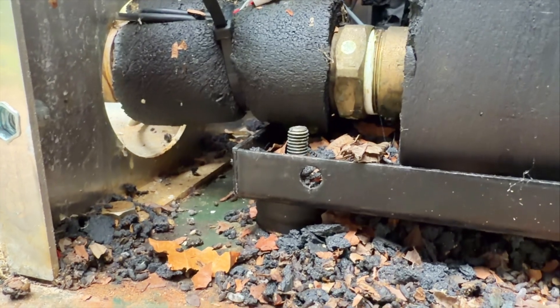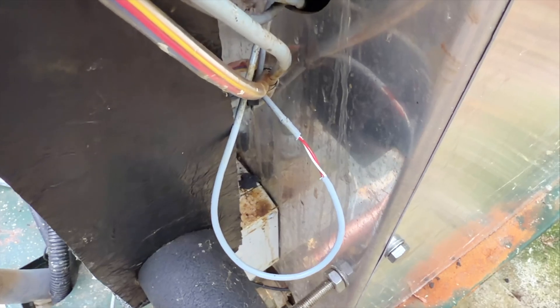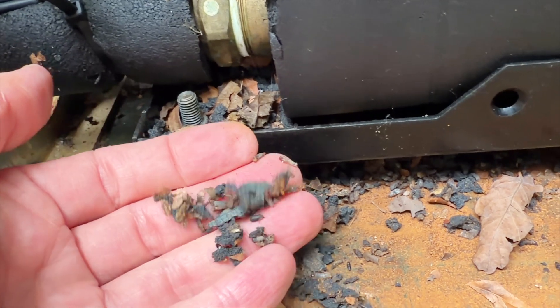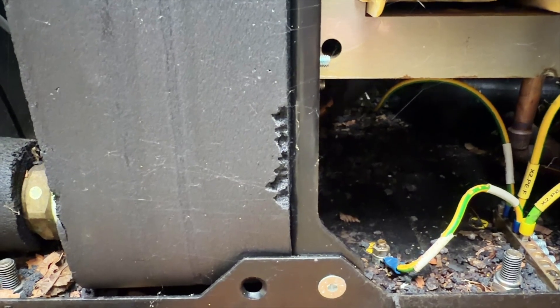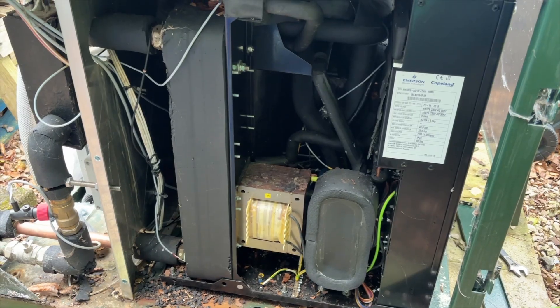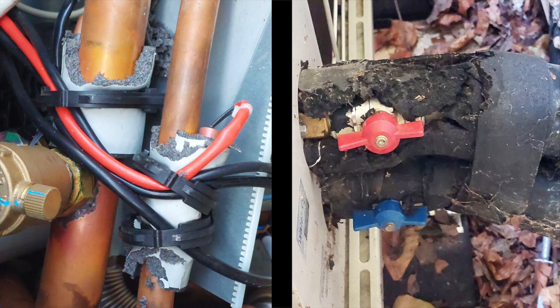That gave them direct routes to warmth and shelter via other access points inside the unit itself. Inside, we found one sensor cable completely bitten through and another half gnawed, with the internal insulation torn to shreds. It looked like a tiny mouse hotel — that soft foamy insulation must be nesting heaven for them: warm, dry, easy to shred, and close to multiple components and pipes that emit a lot of heat.